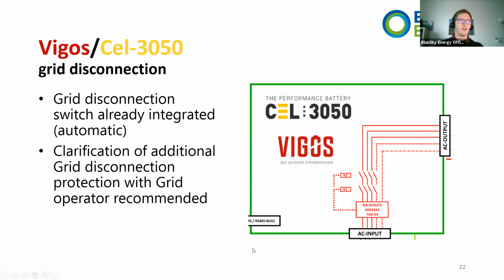So in here, you can see this grid disconnection. This should display a Vigos or a Cel-3050 system. We have 2 connection points for AC. AC input means a bidirectional grid connection point. And the AC output is the emergency backup connection. So if you want to use the emergency backup connection, you can use the AC out connection for that.